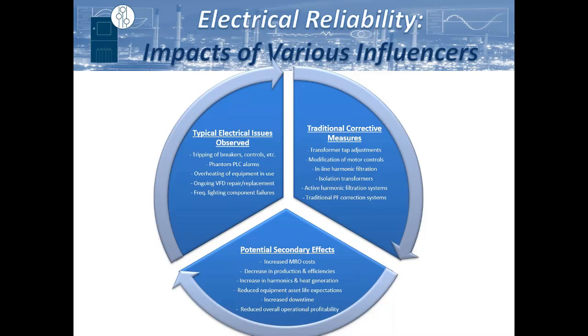So the traditional corrective measures have often been, and I'm sure many of you have seen this out in the field, that in order to ensure that things don't trip out, we'll just go and adjust the tap setting on the transformer. Because every single time you have one of these large loads or a large motor start, that has a significant impact on the voltage level throughout the network. So in order to keep that voltage from dropping too far and having an impact on other systems or processes, they'll tap up the transformer. So, treating the symptom versus necessarily the cause.